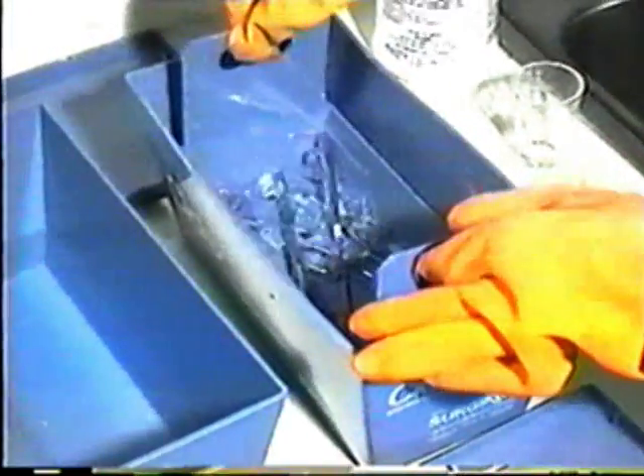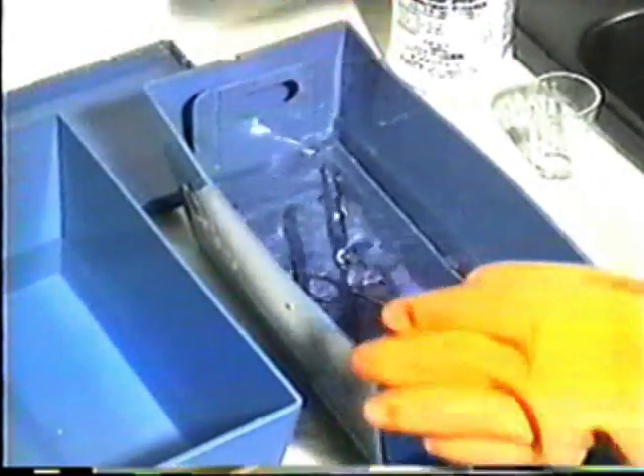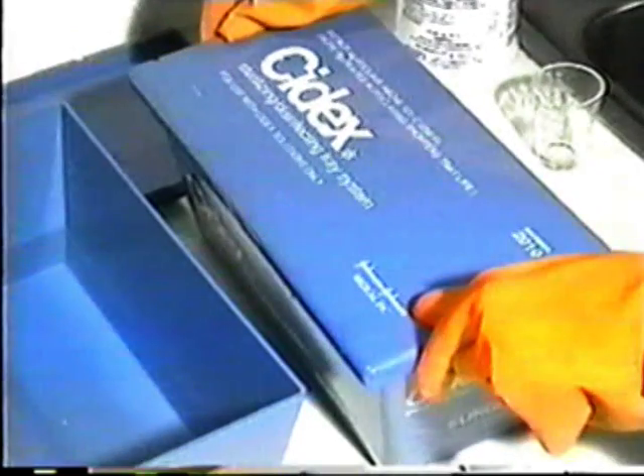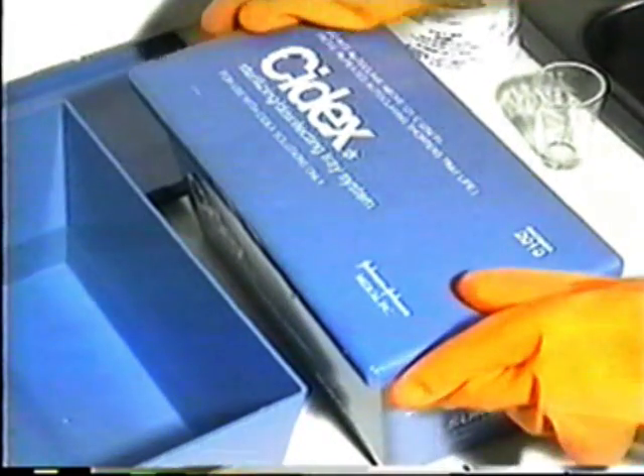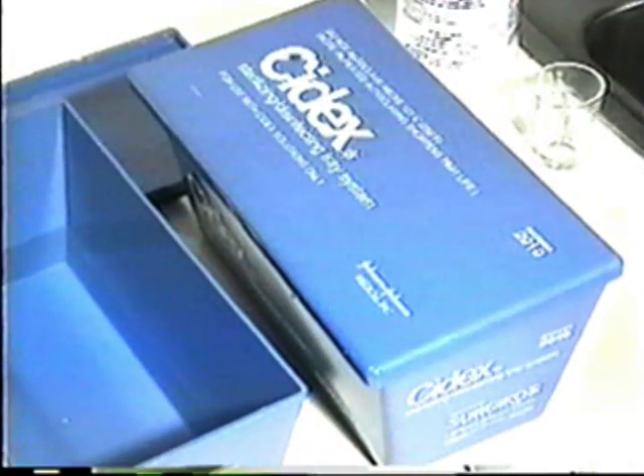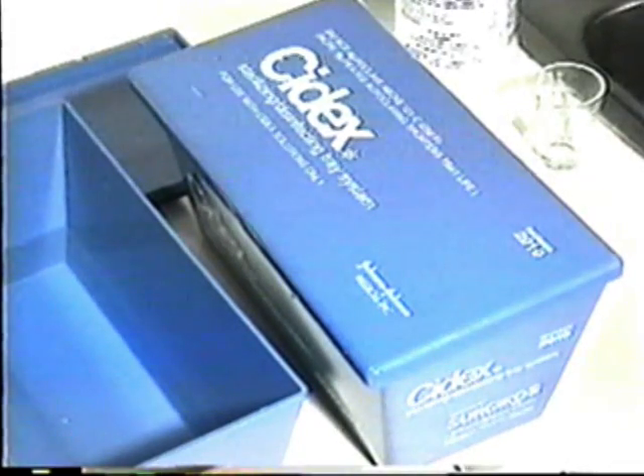Place the instruments in a tray, opening all instruments which have handles. Completely immerse the tray into the solution and close the cover if required. Leave the items in the solution for the required time. Exposure time may vary from 20 minutes to 3 hours or more depending on the chemical used. Correct exposure time is extremely important to ensure complete disinfection.